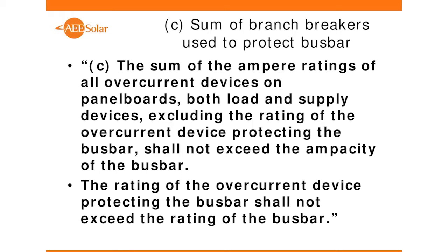So we have the 120% rule, and I think everybody understands that. We got 200 amp from the utility, and it's a 200 amp bus. We could put a 40 amp PV breaker in that. Everybody gets that. But what we never had before was this thing called an AC combiner panel, which is bringing together essentially a bunch of different inverters into a single panel to a single feed that goes on from there. And so people were trying to apply the 120% rule to that combiner panel, right?